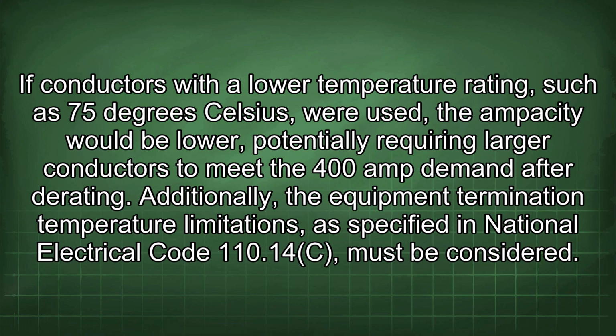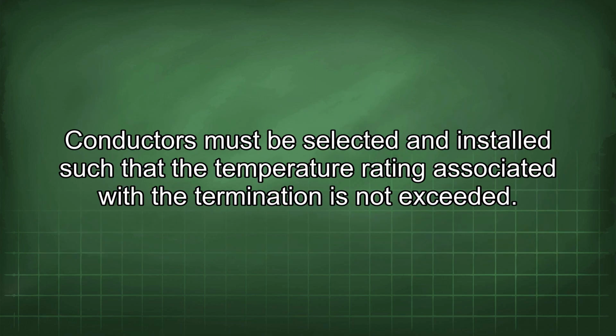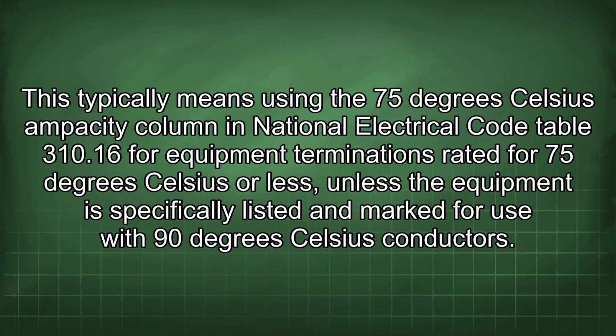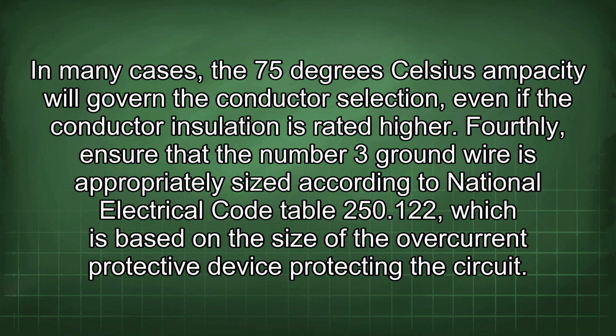Additionally, the equipment termination temperature limitations, as specified in National Electrical Code 110.14(C), must be considered. Conductors must be selected and installed such that the temperature rating associated with the termination is not exceeded. This typically means using the 75 degrees Celsius ampacity column in National Electrical Code Table 310.16 for equipment terminations rated for 75 degrees Celsius or less, unless the equipment is specifically listed and marked for use with 90 degrees Celsius conductors. In many cases, the 75 degrees Celsius ampacity will govern the conductor selection, even if the conductor insulation is rated higher.